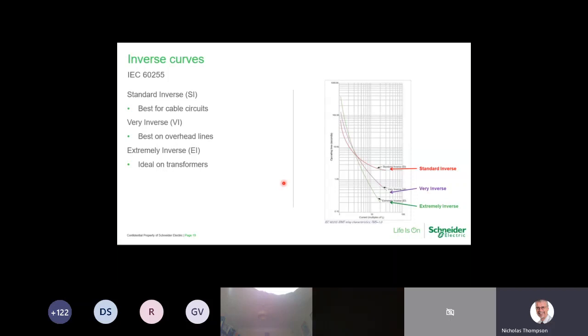Distribution transformers traditionally have been protected using fuses, and these are the HV fuses. And apparently the curve on an extremely inverse curve is the same as a curve used in the fuse. So that's probably why that one is recommended for transformers.